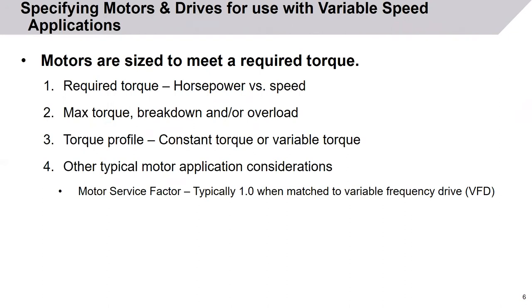To specify motors and drives for use with variable speed applications, first let's talk about motors. Motors are sized to meet a required torque — how much is needed to drive a load — which is a function of horsepower versus speed. You also need to know the max torque, also known as breakdown torque and/or overload capabilities, and the torque profile of the load — whether it will be constant torque or variable torque. One key fact: typically motor service factor is 1.0 when matched to a variable frequency drive.